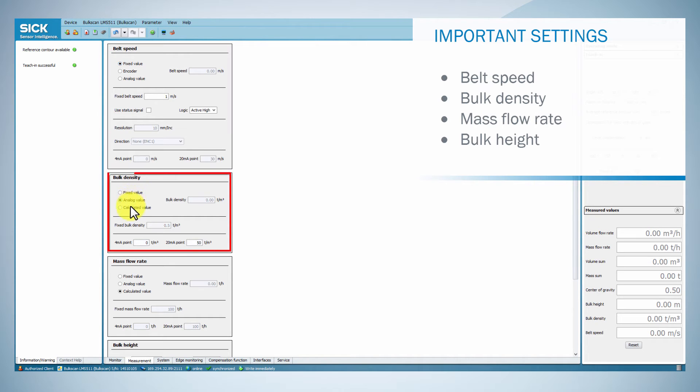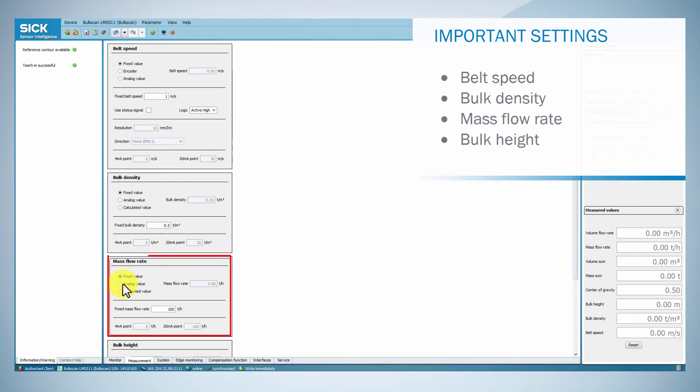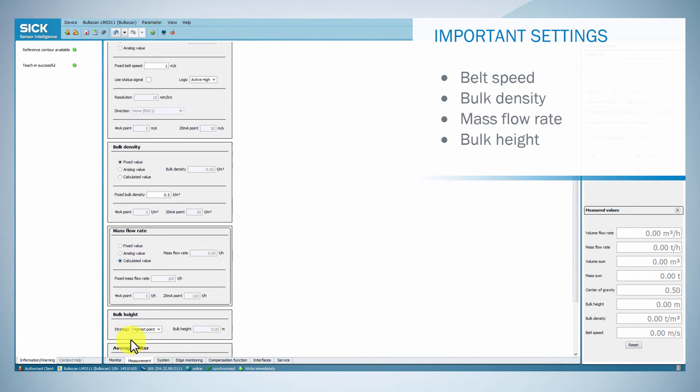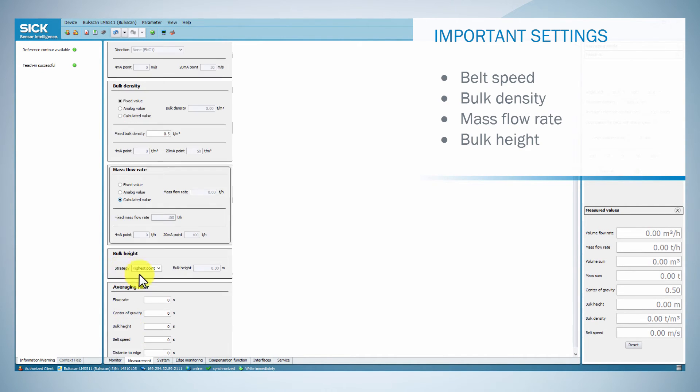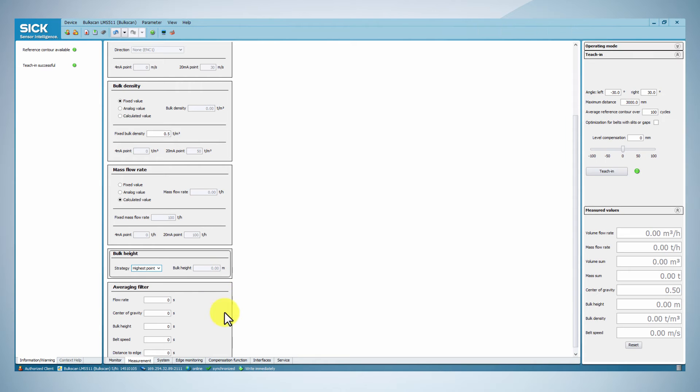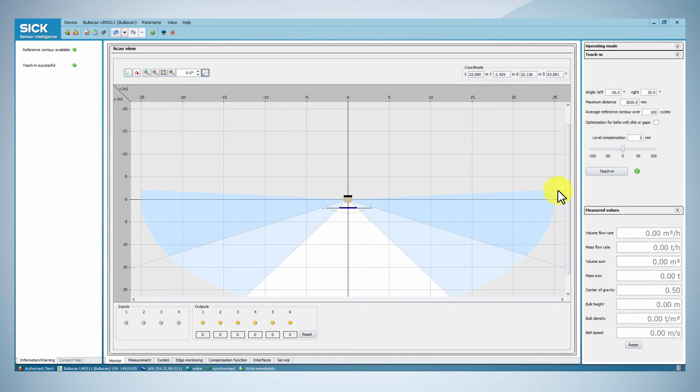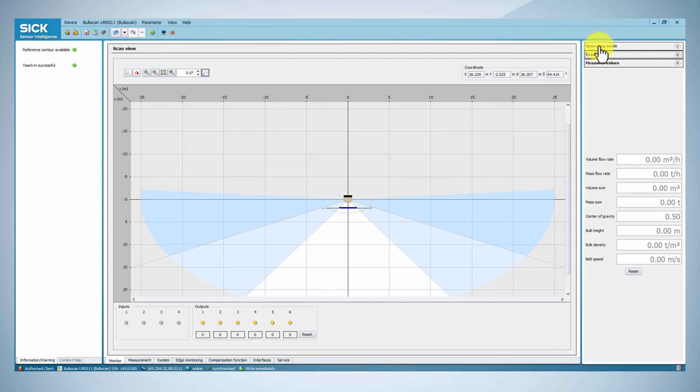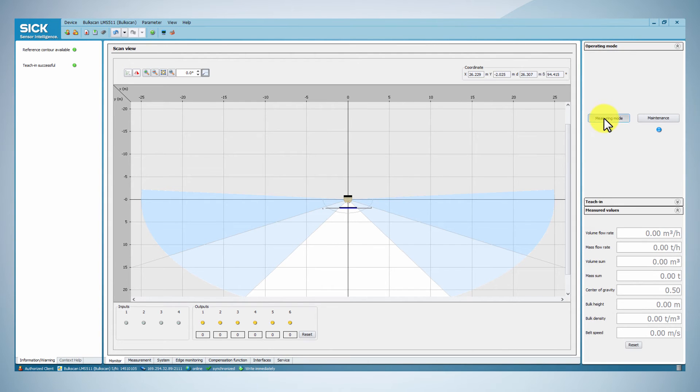If necessary, you can also set up the measurement of bulk density or mass flow rate, as well as a strategy for bulk height measurement. After carrying out these basic settings, you can perform a test measurement, in order to verify the measurement contour and the generated measured value using the scan view in SOPAS.